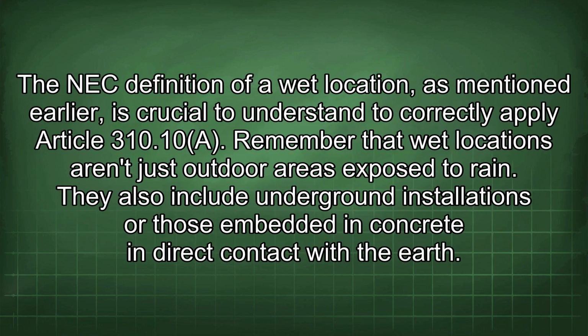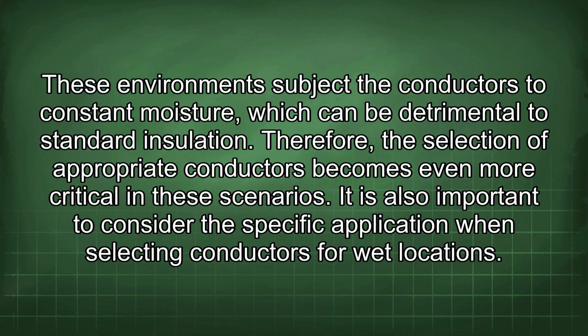The NEC definition of a wet location, as mentioned earlier, is crucial to understand to correctly apply Article 310.10(A). Remember that wet locations aren't just outdoor areas exposed to rain. They also include underground installations or those embedded in concrete in direct contact with the earth. These environments subject the conductors to constant moisture, which can be detrimental to standard insulation. Therefore, the selection of appropriate conductors becomes even more critical in these scenarios.